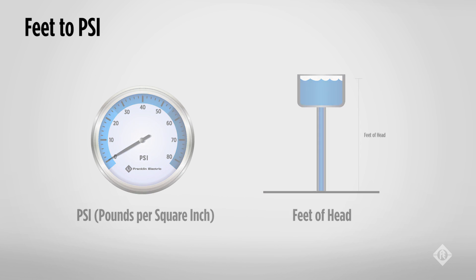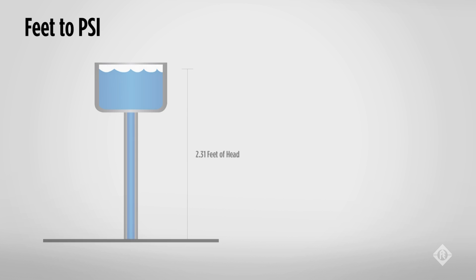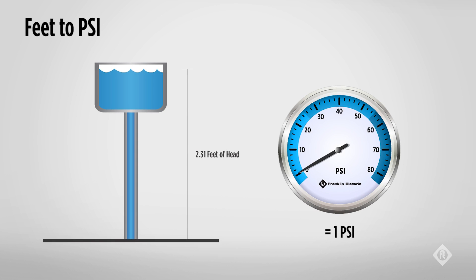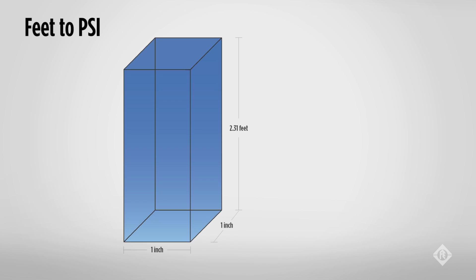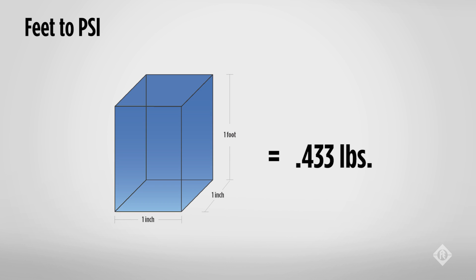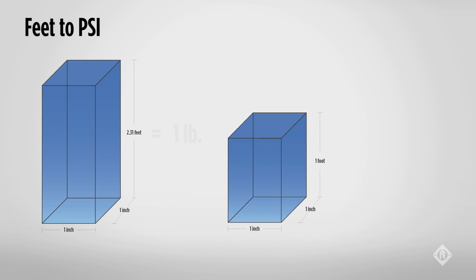The relationship between psi and feet of head is that 2.31 feet of head equals 1 psi. Translated, that means a column of water 1 inch square and 2.31 feet tall weighs 1 pound, or that a 1-foot column of water 1 inch square weighs 0.433 pounds. The two numbers — 0.433 and 2.31 — are the conversion numbers used to convert from one unit to the other.